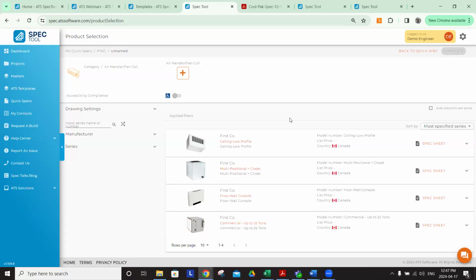So these air handlers or fan coils, there's 4 product options, but depending on the selections that you make, it can be a huge number of products to meet any requirement. So the key message I really want to give, when you come to ATS and look for these HVAC products, is that we do want you to take that next step of configuring the product so that you can get the right BTUs and the unit is going to do what you need it to do.